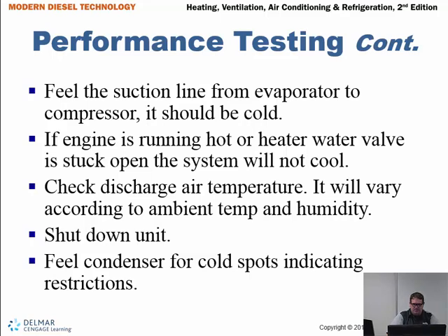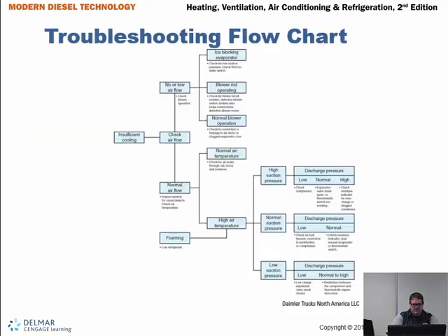Check the discharge air temperature. It will vary depending on the ambient temp and the humidity. And then shut the unit down and feel for cold spots indicating restrictions.